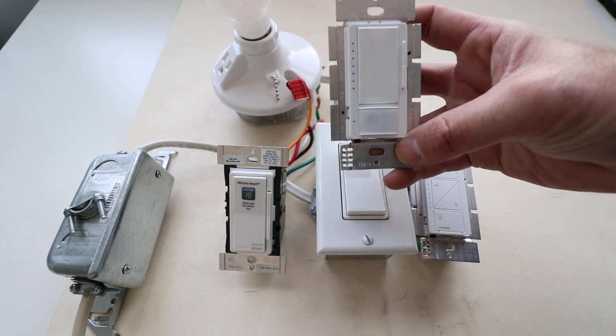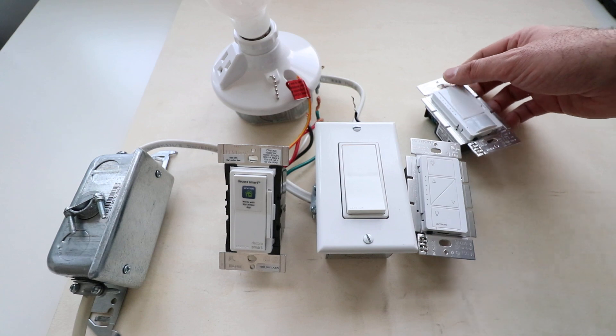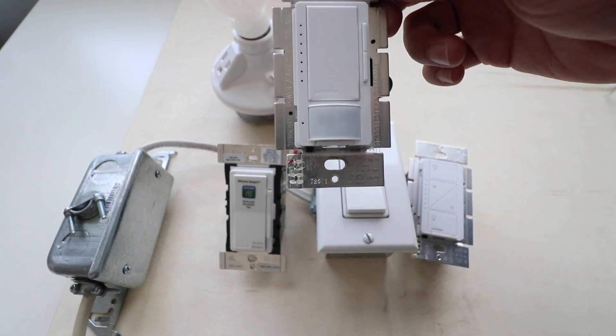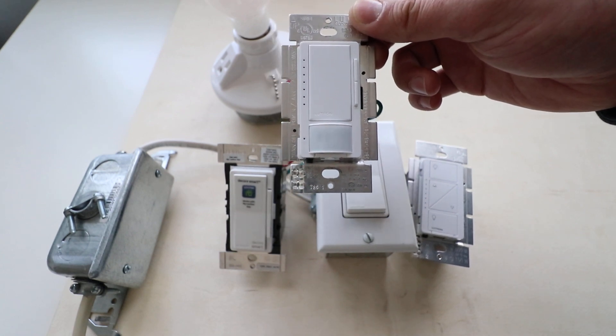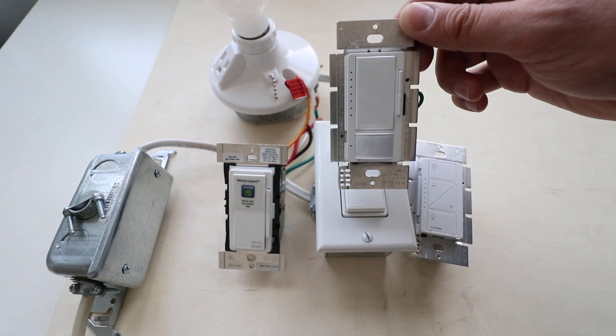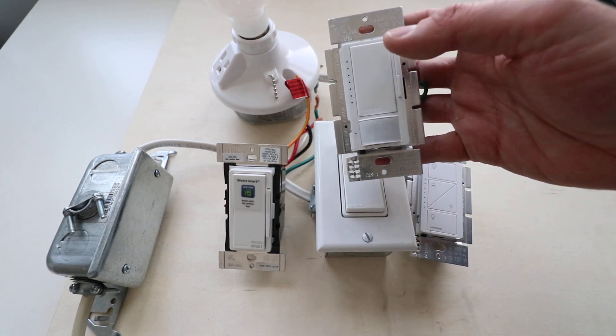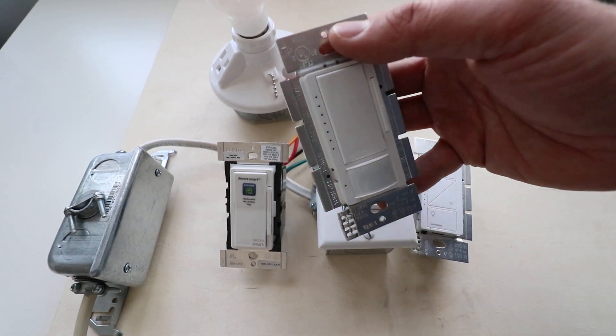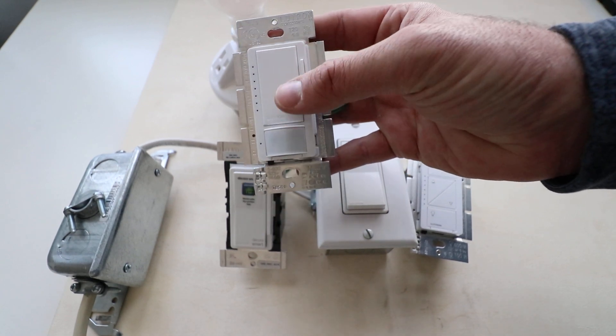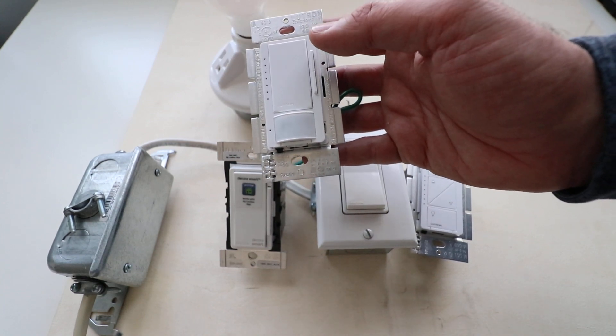So why do I have this one? In residential areas like your living room and kitchen, you've got to have a dimmer in California to be compliant — you can't have the on-off switch. But in spaces that are typically unoccupied or have a low occupancy rate — garages, utility closets, laundry rooms, and bathrooms — they all have to have an occupancy sensor, which means a motion-sensor-activated light switch. The reason is that people will forget to turn the lights off in those spaces, so the intent is that these will automatically turn the lights on and off after motion is no longer detected.